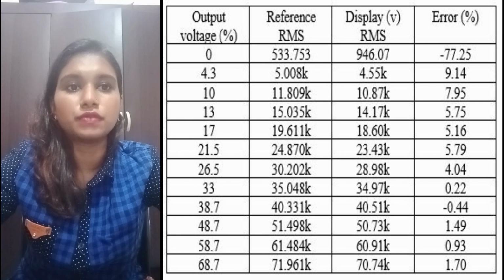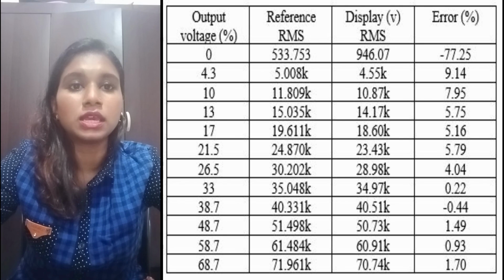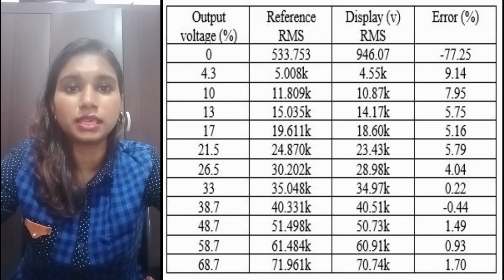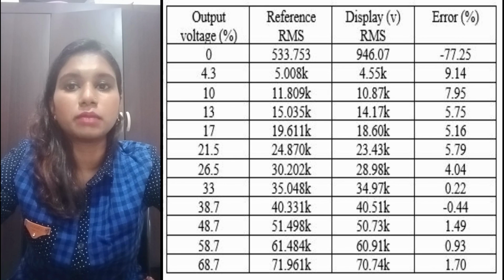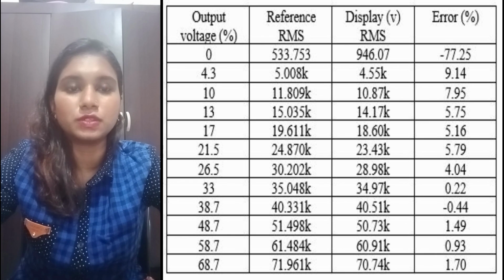On the other hand, for the acquisition settings, the number of sampling points should be set from 0 to 100K sampling, which is the highest value. The 100K sampling means that one period of time has 100K discrete sample points. The higher the sampling value, the better the waveform output. The waveform was also taken by increasing the percentage of output voltage. So from the increments, two values have been obtained, that is the RMS value and peak over square root 2. From there we compared with the reference value and found the error percentage to see the difference between the reference value and the display value. Thank you.